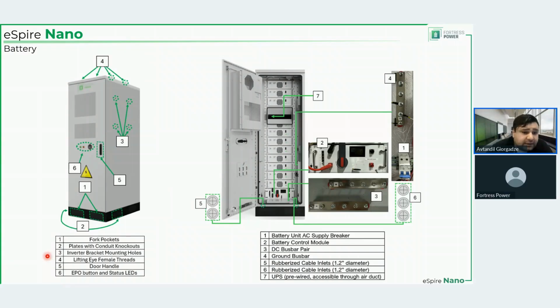Then we have plates with conduit knockouts on the sides. So number 2 here and on the other side as well. Each of them has 3 conduit entrances. That's what I was talking about before, when I said that 3 metal conduits are included for you to connect between the inverter mounted on the side and the battery itself. Those metal conduits will run from the inverter to this plate, and the plate itself also has 3 knockouts because you're getting 3 metal conduits. The door handle is obviously here. The inverter bracket mounting holes that I was talking about are here. You have the status light and fault light, and the e-stop button for the battery is also right here.